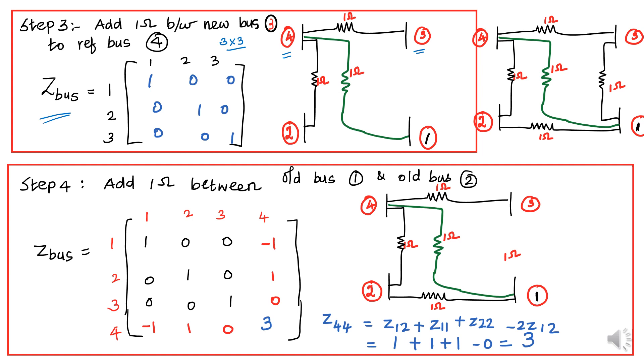Then step number 4: Add 1 ohm between old bus 1 and old bus 2. Here the order of the matrix is increased by 1, giving a 4x4 matrix. But the actual Z-bus matrix should be 3x3 only. Therefore, the last column element and the last row element must be eliminated.